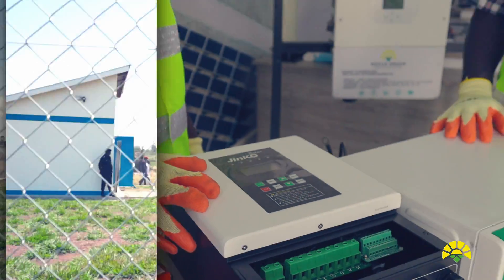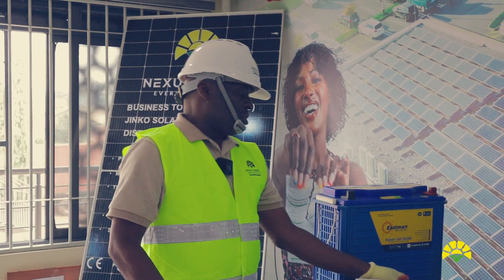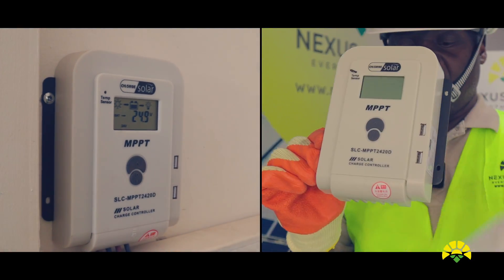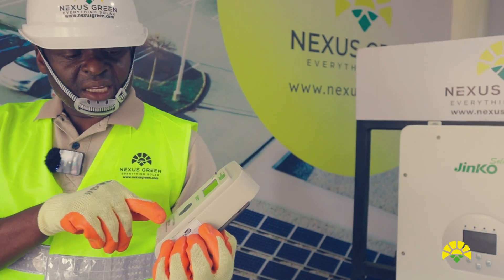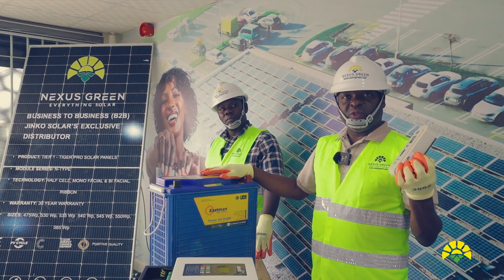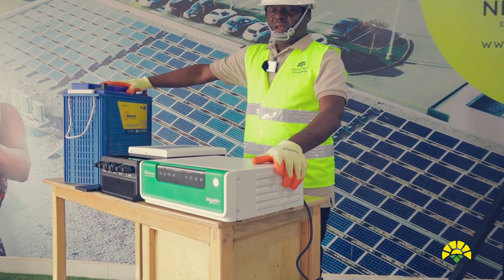Since Nexus Green is exhibiting green energy, we use solar panels to provide electricity for all these pumping systems. From the solar panel, we use an MPPT charge regulator — a 20 amp MPPT charge regulator connected on the solar module, with the other end connected on the battery. This charge regulator controls the charging of the battery, preventing overcharging or over-discharging. From the battery, we connect the auxiliary lighting inverter. We are using Schneider. This inverter provides electricity used in these pumping systems.